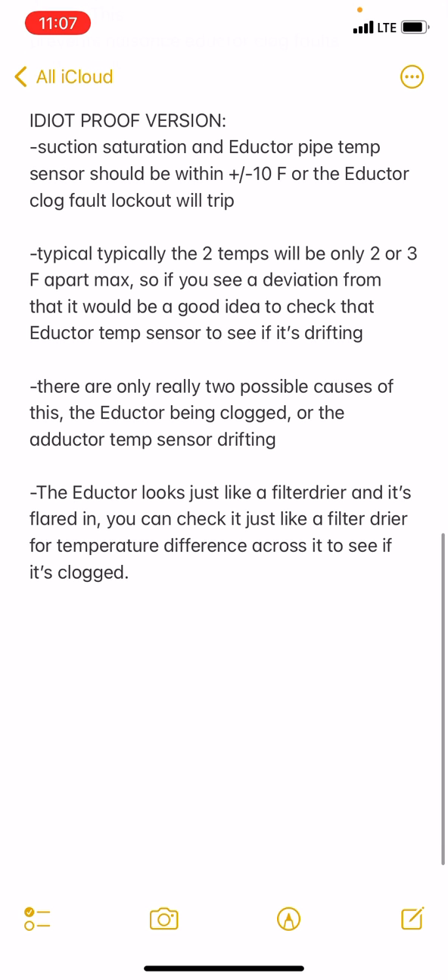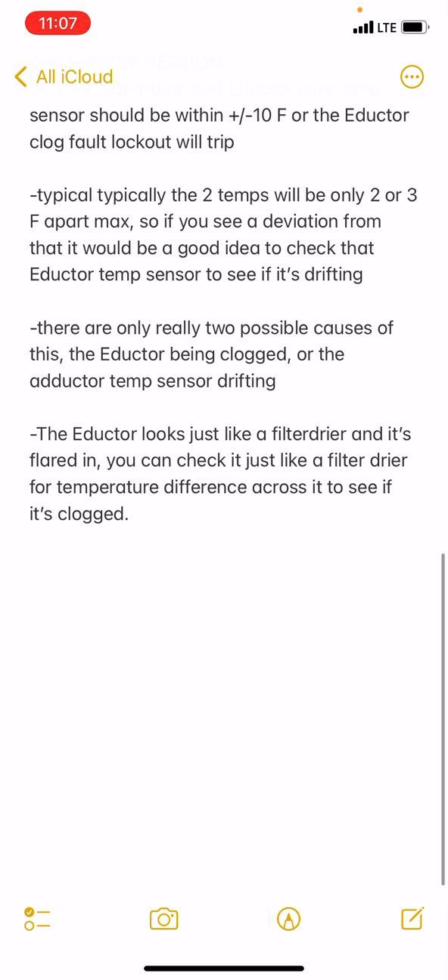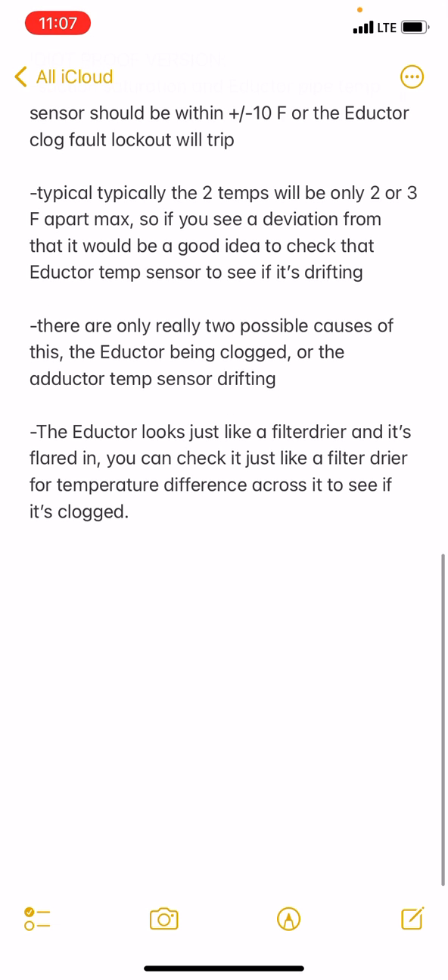Normally the Eductor temperature and the suction saturation will be within two or three degrees or so max — they're going to be very, very close together. There are only really two possible causes of this fault code tripping: the Eductor itself actually being clogged, or the Eductor temp sensor drifting.